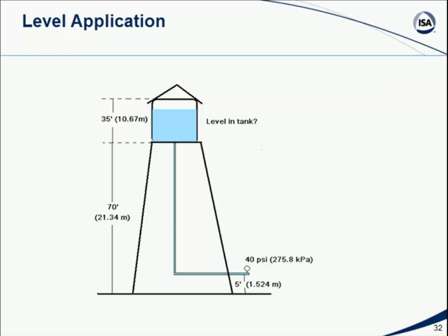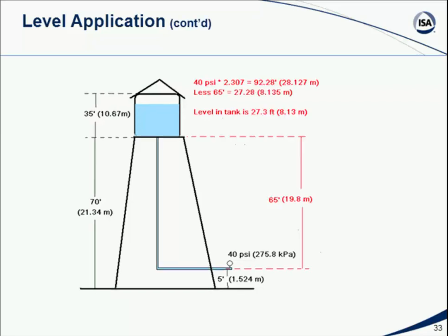And we can do that all by just having a pressure measurement down near ground level and knowing that that pressure is being taken 5 feet above and that we've got a 70-foot minus 5-foot column of water. Right? So we can do the math and do the calculation and find out that, in fact, we have the distance minus the level in the tank, and we come up with the fact that we've got, as I said, 27.28 feet of water in the tank itself. Okay? So this is where being able to do hydrostatic measurement is handy. It might be very difficult to get up and put some kind of level measurement device up in the tank, but we can certainly take a pressure measurement down near the ground.